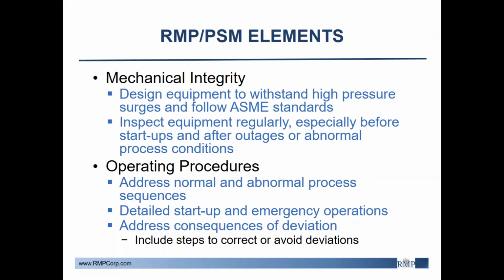Also, it is recommended to design equipment to withstand unexpected system conditions, decreasing error margins and limiting the damaging effects of a failure. Regular inspection of equipment is also essential to keep equipment up to design codes and should be done frequently, especially after system shutdowns and before restarts. If an equipment walkdown had been done before the MILLARD refrigeration system was turned back on, the presence of hot gas would have been detected and could have been removed before starting. Therefore, a strong mechanical integrity program can significantly help prevent serious accidents.